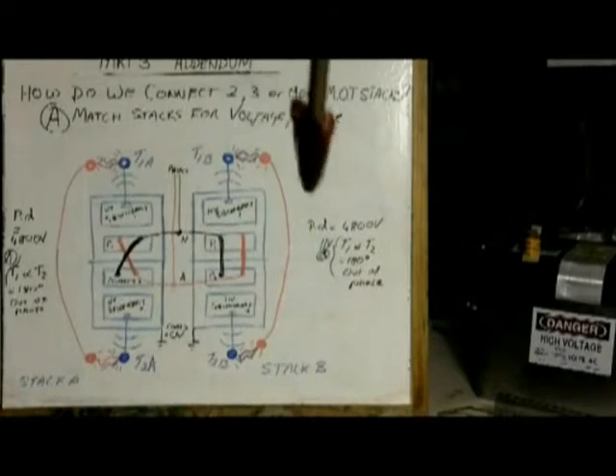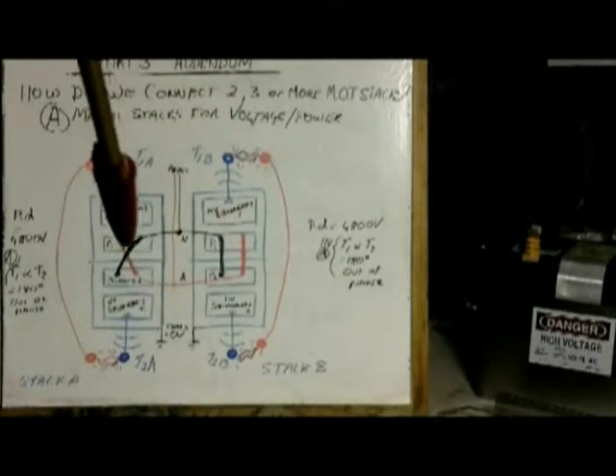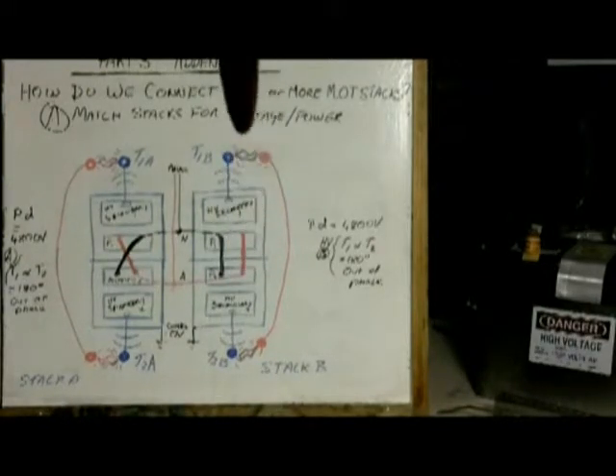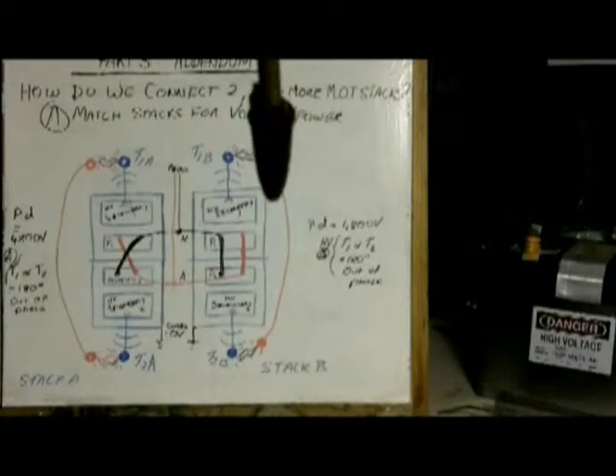So as I just said, these 2 stacks are just standing side by side. They're not actually connected together. The only thing connected is the primaries, because they're sharing a primary. You've chosen one for the active, is drawn in red, and one for the neutral. These are hardwired. Not going to touch these hard wires anymore, just as when you've created the stacks, you've created them for that 180 degree phase out of phase combination. Okay, the cores are at 0 volts because they're grounded.